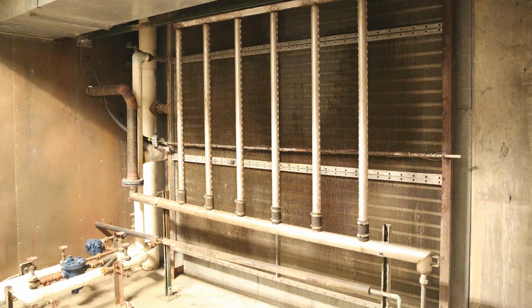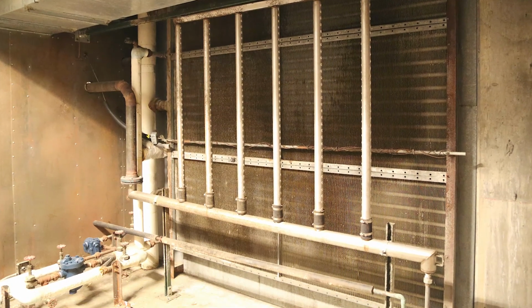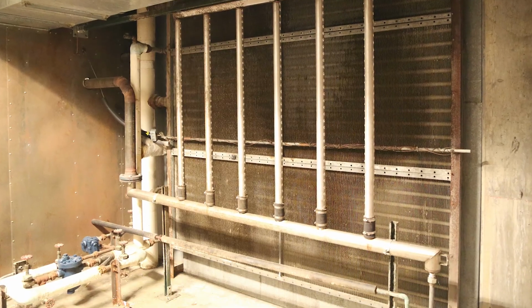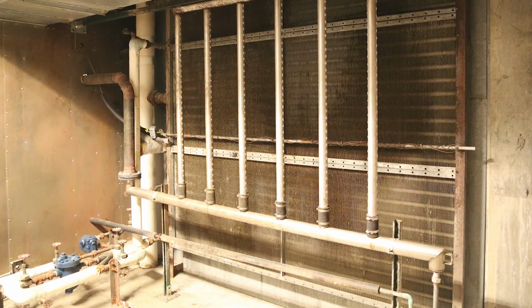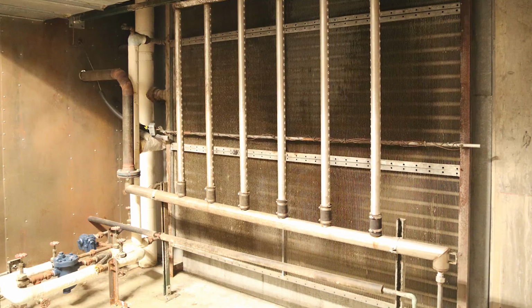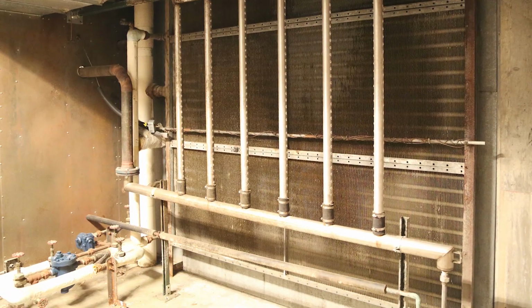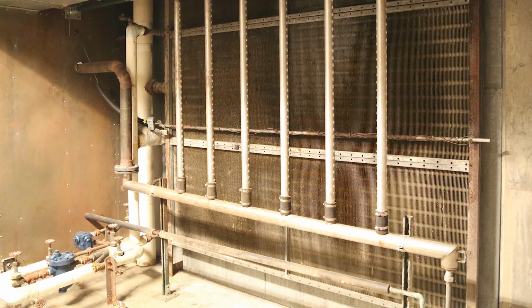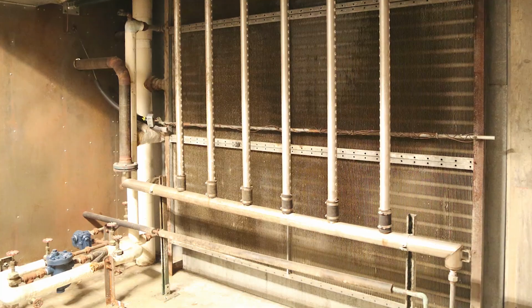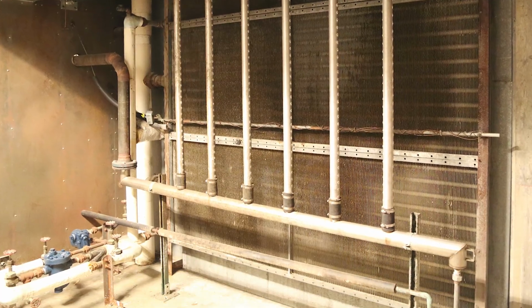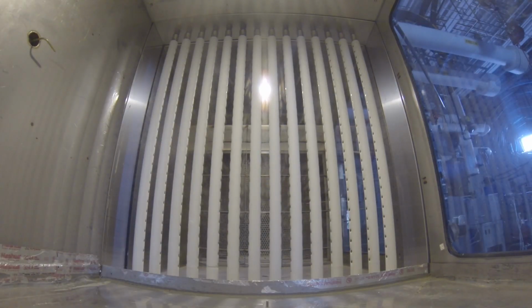So going back to, if we're going in an air handler, you're shoving the entire dispersion array within the air handler. And you've got your connection to bring the steam in, a drain connection, and potentially some structural support. That's outside of the potentially the airstream. We want to have the steam in contact with as much of the air as possible, because then it'll dissipate faster. It'll take a shorter distance to basically absorb.